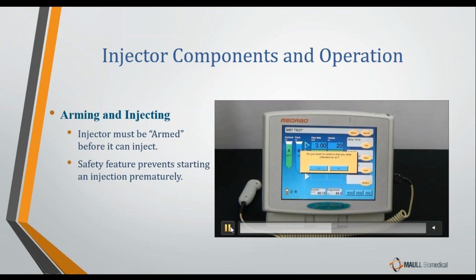Now, as soon as we hit the arm button, pause, a message pops up, and this is true of all contrast injectors. During class, I call this the point of no liability return for the OEM, for the manufacturer. Whenever the operator hits the arm button, which you saw me do right here, a little message is going to pop up. Different models have different messages, but the gist of the message is always the same. Do you wish to confirm that you have checked for air?